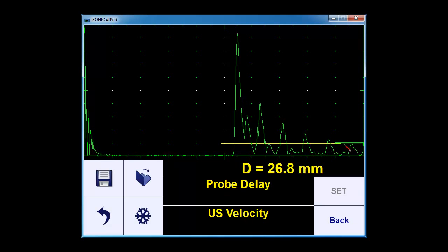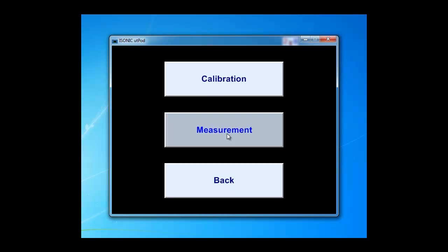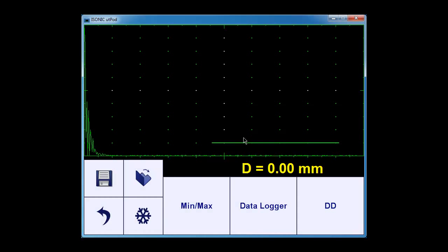and again choose the gain properly so that my range is covered. Now I see 4 mm is shown here, probe delay and sound velocity are also automatically measured. Now the calibration is done.